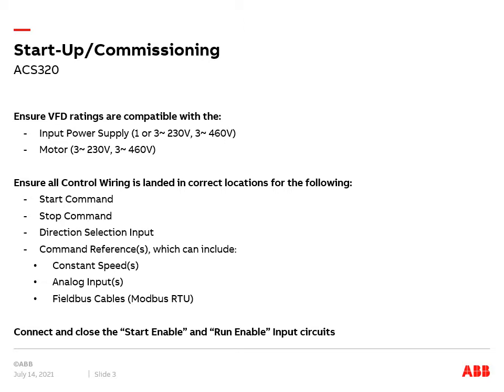The level and type must match the drive. This can be confirmed from the information on the VFD serial number label. Drive and motor compatibility must also be confirmed. Ensure that your drive has appropriate voltage and current ratings for the specified motor. This information can be confirmed from the VFD serial number label and the motor nameplate.